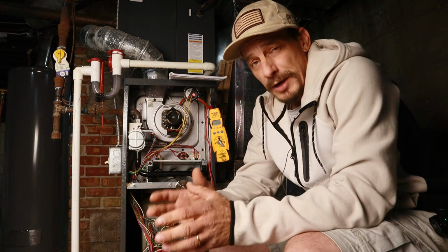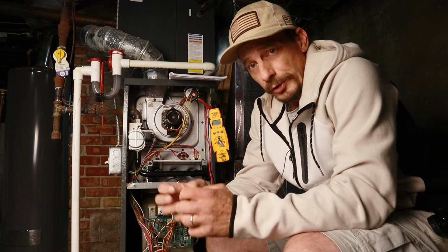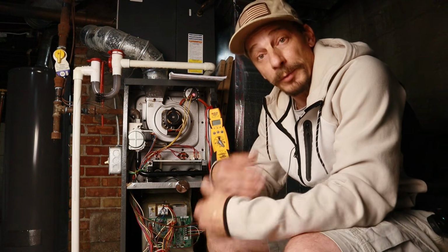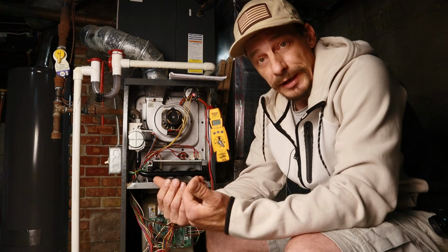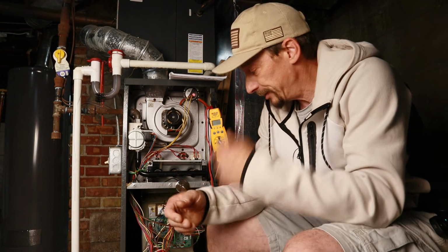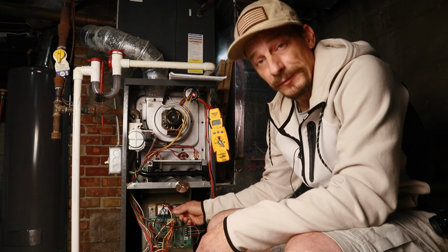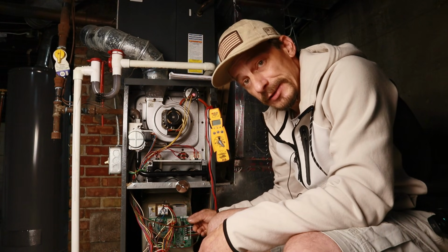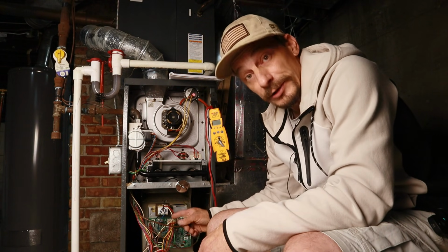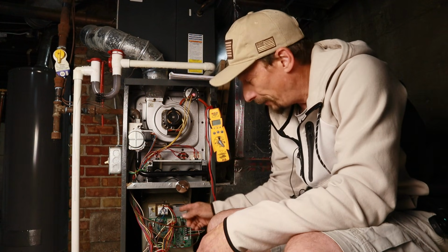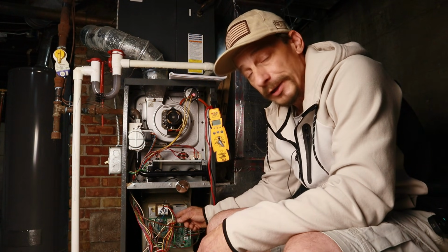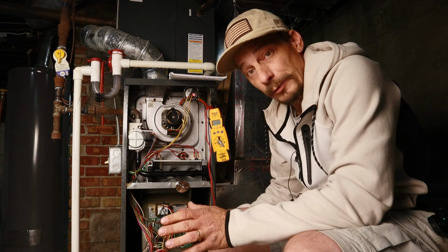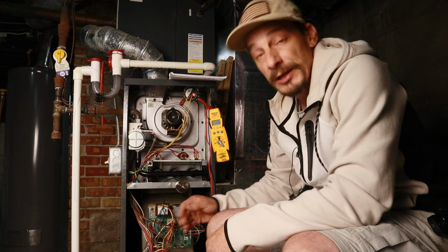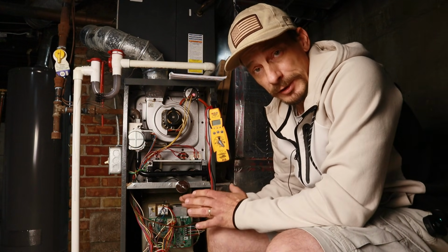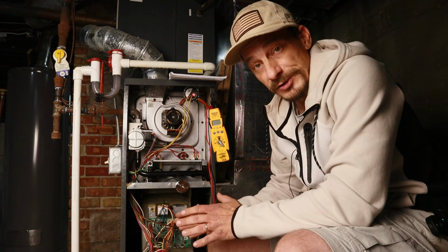Now, schematics are not going to show you the internal wiring on the control board itself, but what I just told you is pretty standard for most furnaces. You're going to have the power coming off the transformer, going back into the control board, and directly to the fuse itself. Now, the power coming into the control board is just going to the fuse. It's not going anywhere else, and the whole purpose of the fuse is to protect the control board itself from shorts in a low voltage circuit.